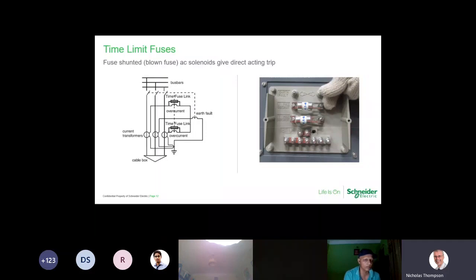The principle of operation is very simple. If the secondary current out of the CT exceeds the fuse size, then because of the impedance of the coil, and the fuse impedance is much lower than the impedance of the trip coil, the current will flow through the fuse. Naturally, if the CT current is higher than the fuse size, then the fuse will blow. And then once you've blown the fuse, the only path for the current to flow is through the trip coil, and then the trip coil will operate. And because of the tripping platform, it's going to open up all 3 phases.